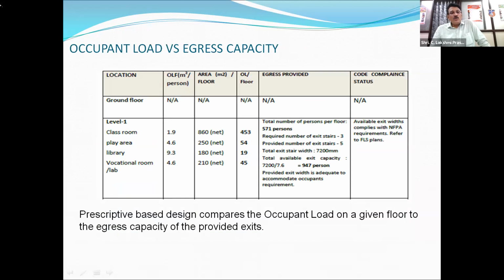Then occupant load versus egress capacity. This is just a general calculation. It is a very simple thing. Once you arrive at the occupant load, you just calculate with the factor that is given in the table. Then you will arrive at the effective exit width. And apart from this, you have to see two other things, that is travel distance and the dead end corridor.